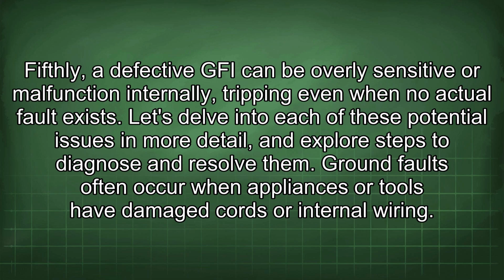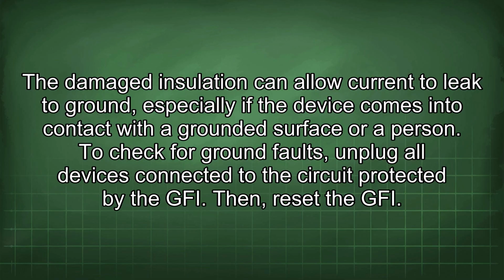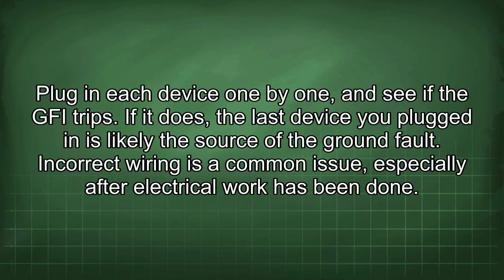Ground faults often occur when appliances or tools have damaged cords or internal wiring. The damaged insulation can allow current to leak to ground, especially if the device comes into contact with a grounded surface or a person. To check for ground faults, unplug all devices connected to the circuit protected by the GFI. Then reset the GFI. Plug in each device one by one and see if the GFI trips. If it does, the last device you plugged in is likely the source of the ground fault.